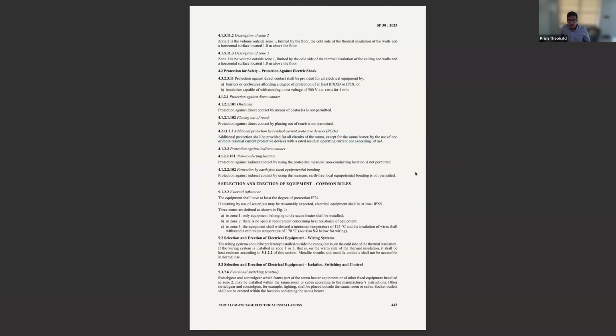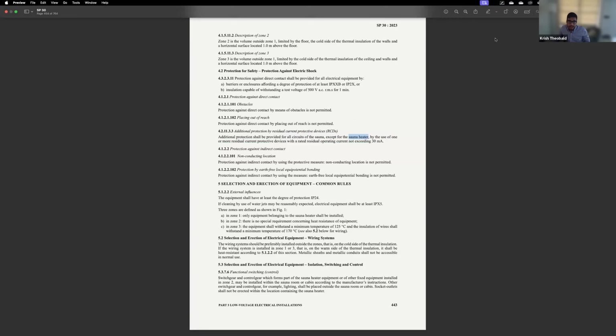So, if it's a TN system, every circuit except the heater requires RCD protection of 30 milliampere. If it's a TT system, then every circuit requires an RCD of 30 milliampere, except for the sauna heater, where you can use 100 or 300 milliampere as required. Now, when it comes to the type of RCD required, that depends entirely on the heater itself. What kind of a circuit is it?